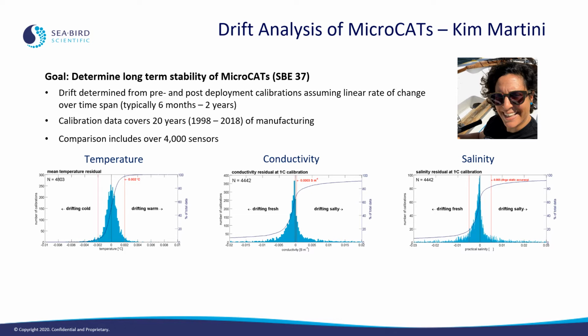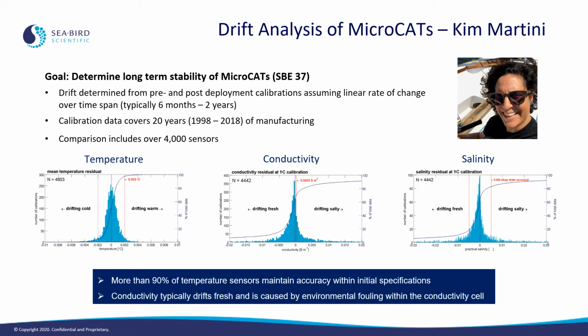different sensors. You can see the results in the plots below, temperature on the left, conductivity in the middle, and salinity on the right. The vertical lines in the plots indicate the initial instrument specifications, and what you can see is that there's really no bias in temperature, and over 90% of the temperature sensors maintain their accuracy within the initial specifications. There is a bias in salinity that is slightly fresh and is most likely caused by environmental fouling of the conductivity cell. The next steps here are really to look at the actual drift rates, and that's to be done soon.